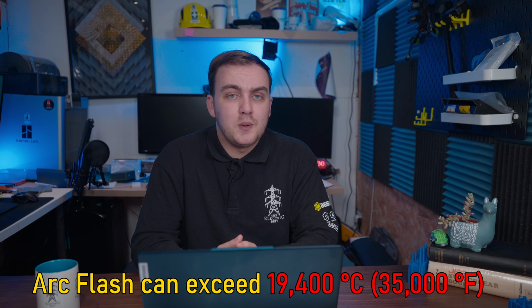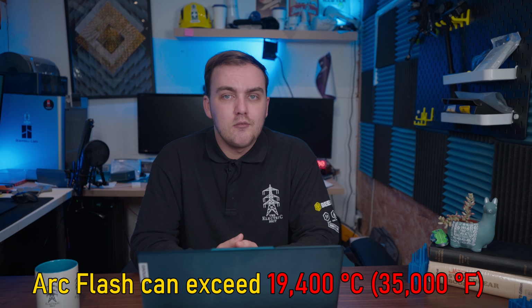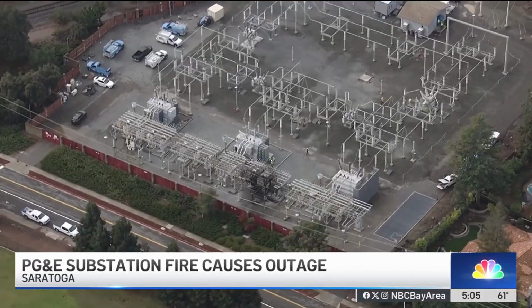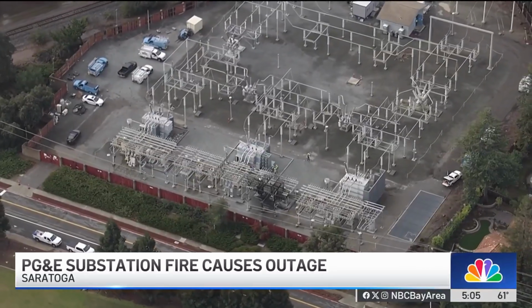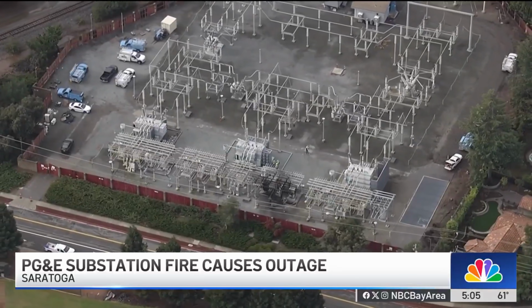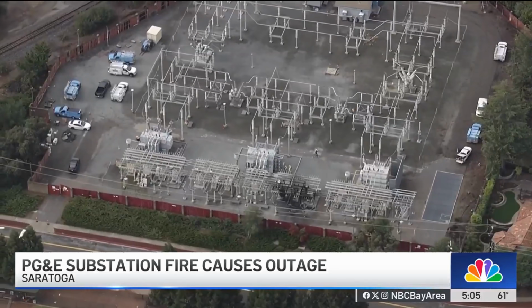But to leave these pitch black carbon deposits everywhere, you really need to be burning a hydrocarbon, like oil. This means this was an oil circuit breaker which catastrophically failed, spraying its oil everywhere, travelling down the bus bars and burning, until it burned itself out. Now it's also worth mentioning that when the fire brigade turned up, they opted not to fight the fire, and that's the right call to make. The amount of oil given off would have been pretty small, all things considered, and everything in there is stone, concrete and metal. It would have self-extinguished pretty fast.